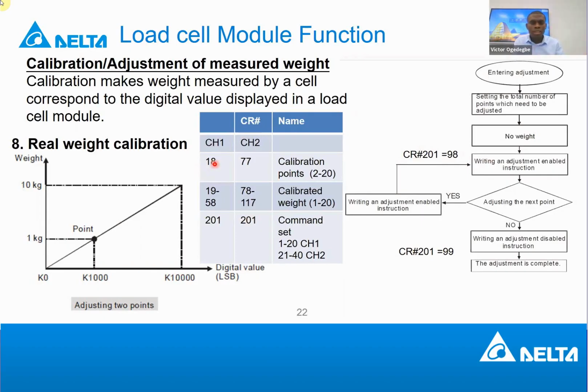number 3. This is one way, let me not confuse you. What I've explained is with the control register: you specify the number, then you specify the digital value, you enable calibration, and it's like a loop. You continue until the number of points you want to calibrate. That is one way. Another way that's possible is this. Let's go to the software. That was with the control register. You write, we use TO and FROM.